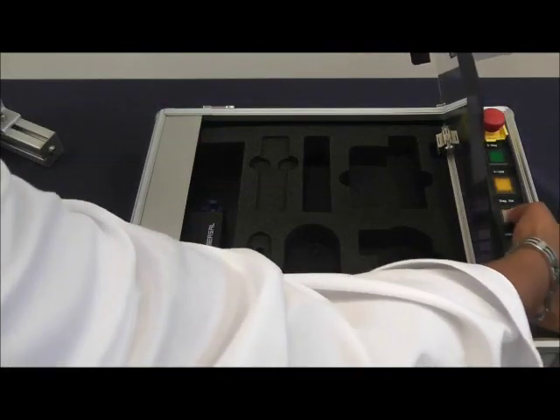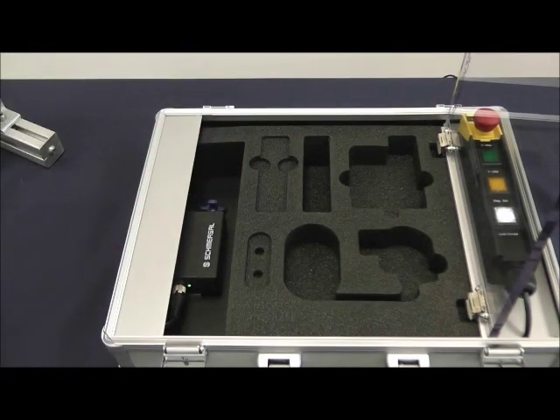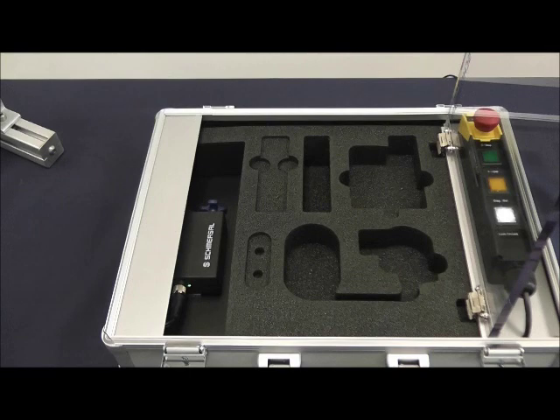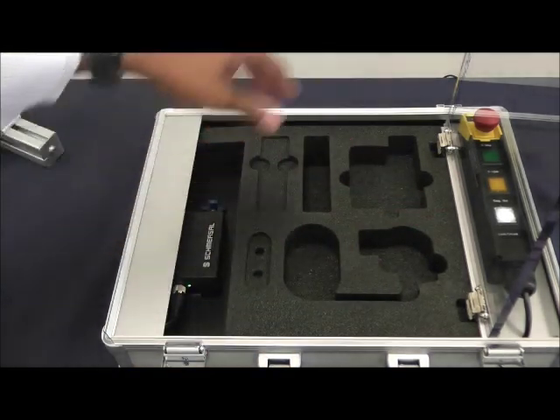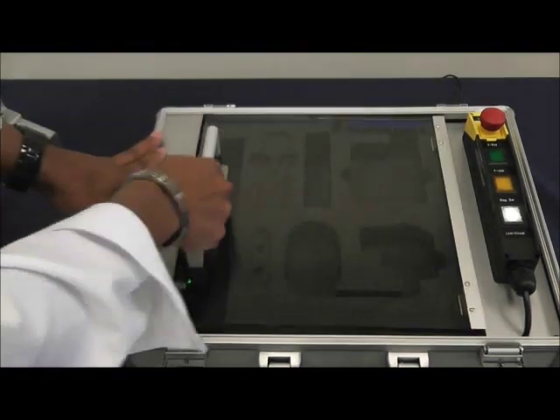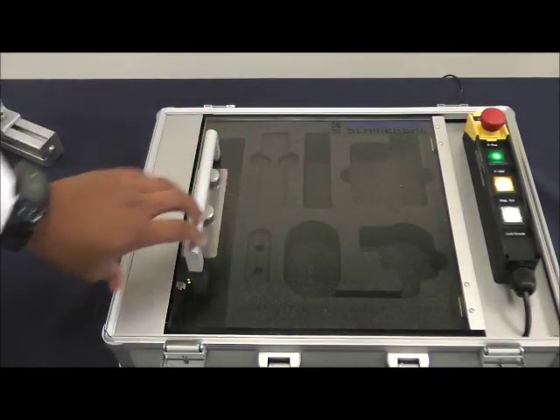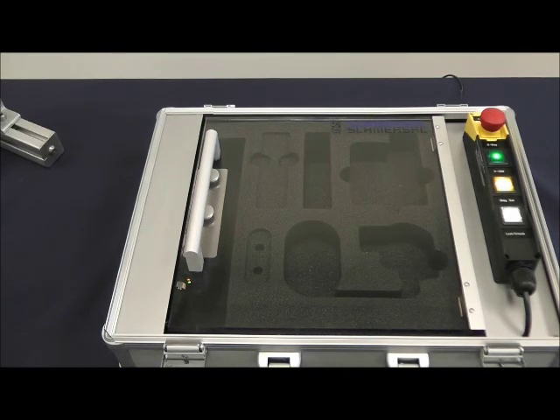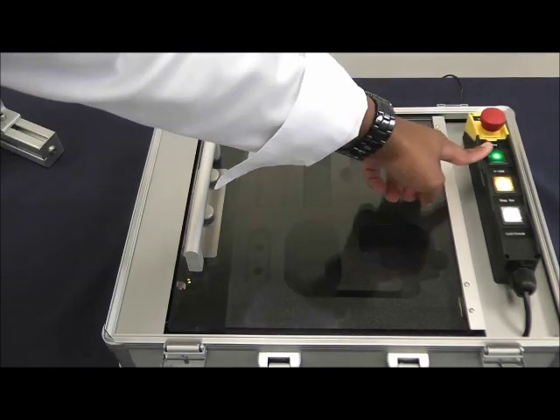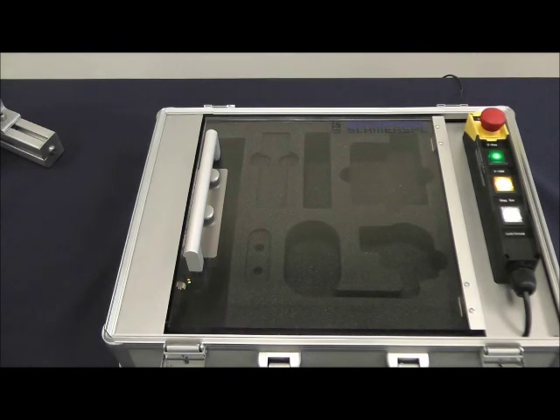So going back to the idea of how you can damage the locking mechanism for solenoid switches. So let's go ahead and send our lock signal. And conventional devices, as soon as you close the door, the switch will lock. And again, if you have a heavy door with bounce back and the switch is not mounted or installed correctly, you can have the possibility of damaging the cam mechanism over time. So now we have our lock signal to our AZM300. And let's say this is a big door with the possibility of a bounce back. Notice that the AZM300 has a short 200 millisecond delay, which allows the door to bounce back open so we're not adding stress to the locking mechanism. And as soon as the door is closed, you have your safety outputs because we already applied the signal for locking. So that brief 200 millisecond delay allows you to maintain the integrity of your locking mechanism even if you have a large door with the bounce back.